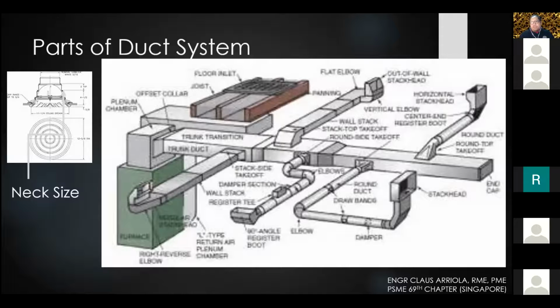depends on the complexity of your design. Okay, sometimes it can be like this, but sometimes it's just a plain straight duct with all your grills or grills with motorized dampers. Okay, but as much as possible for engineered smoke control, we need to limit the system pressure loss. Of course, the more bends, what is system pressure loss? It is the loss of pressure from your fan to the last terminal. Of course, if you have so many bends, then you will lose a lot of pressure, right?